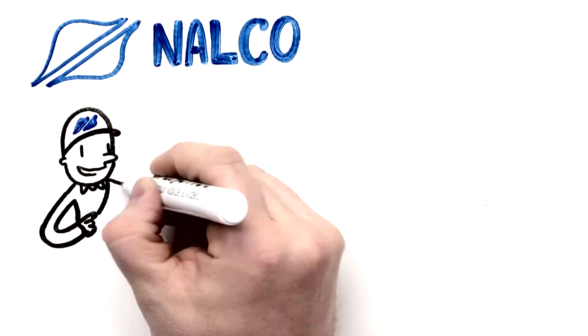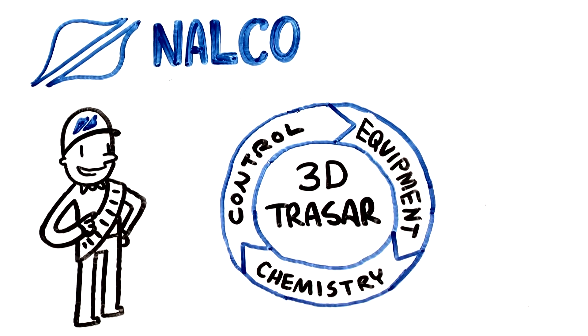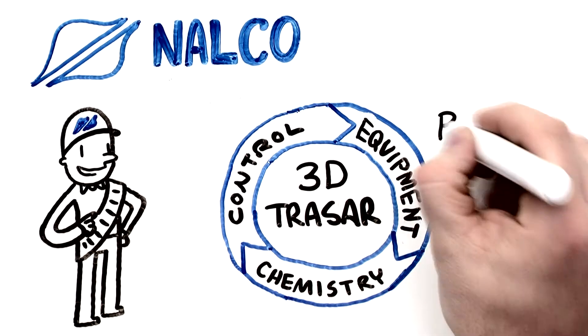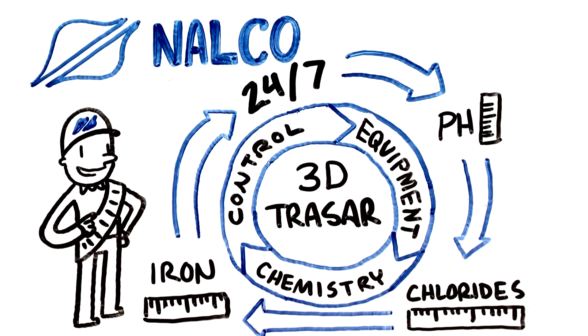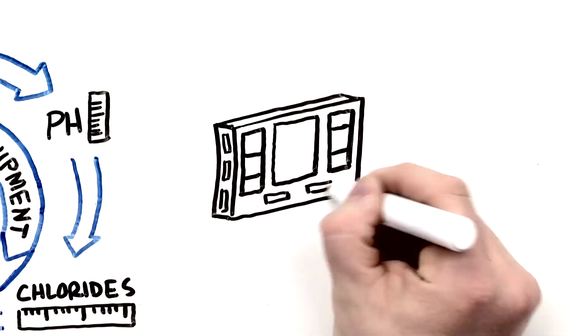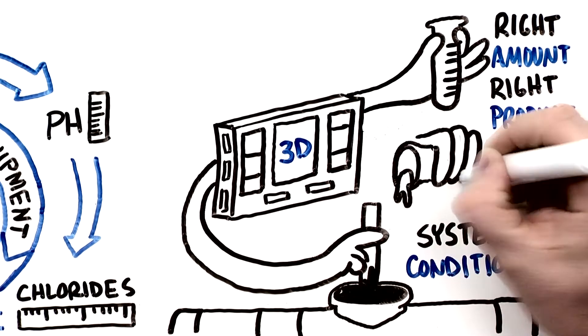NALCO understands those challenges. We combine chemistry with equipment and control schemes like 3D TRASAR for crude units, allowing us to continuously measure pH while measuring chlorides and iron up to 24 times per day. 3D detects system conditions, determines the right amount of the right product, and delivers it.